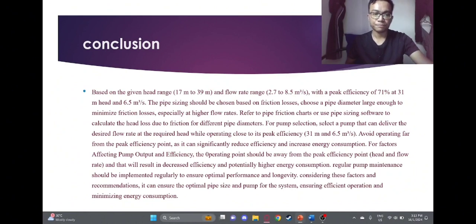And lastly is the conclusion. Based on the given head range and flow rate range with peak efficiency, the pipe sizing should be chosen based on friction losses. Choose a piping diameter large enough to minimize friction losses, especially at higher flow rates. Refer to a pipe friction chart or use pipe sizing software to calculate the head loss due to friction for different pipe diameters. For pump selection, select a pump that can deliver the desired flow rate at the required head while operating close to its peak efficiency.